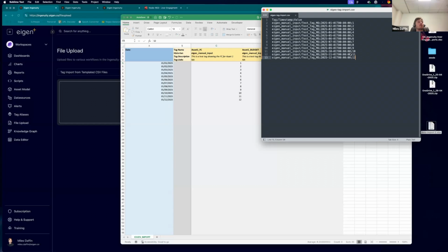The benefit of using something like this versus just a static point is that these points get saved in time. So if you click and trend on a threshold calculation, you'll see that threshold will have dynamically changed throughout the period of time. So if you hard code a threshold of 10, it'll be 10 forever, versus if you write that threshold as a point, then today it's 10, but yesterday it was 11, for example. So it gives you a little bit more history. So I think the way Denise showed it would work perfectly for her case.